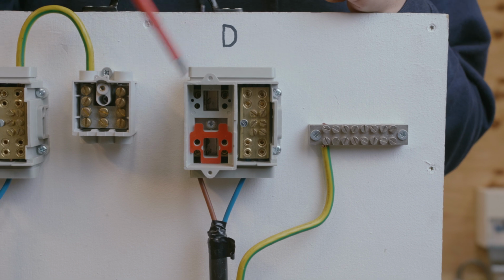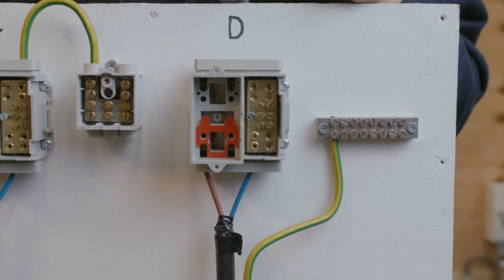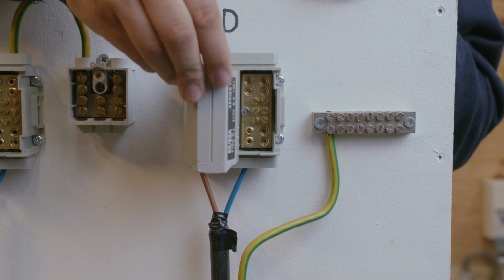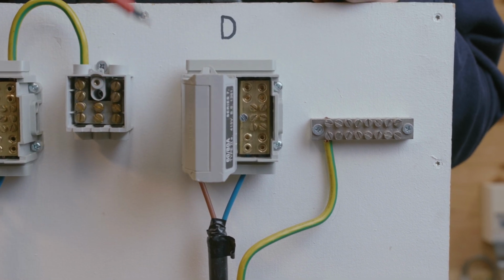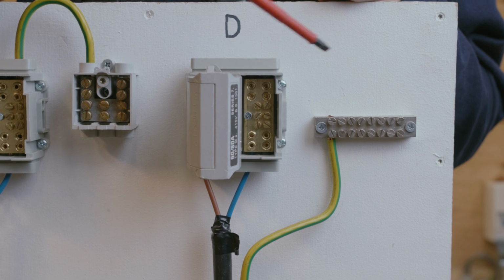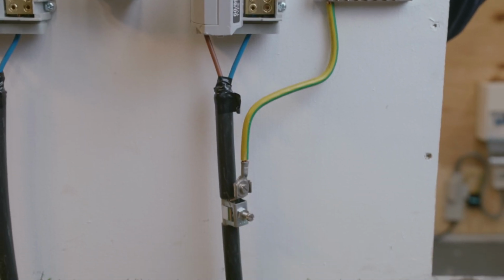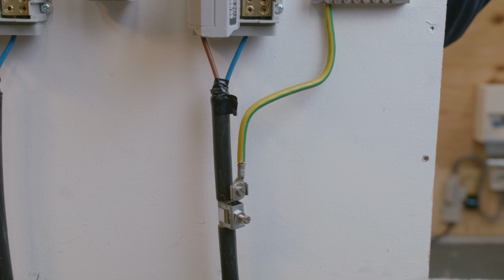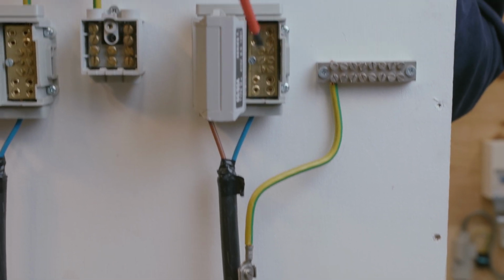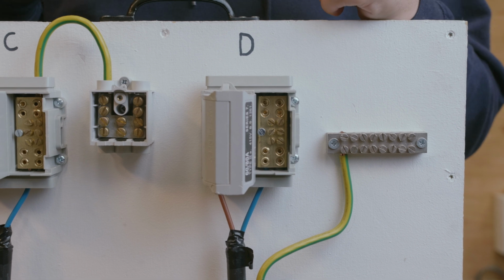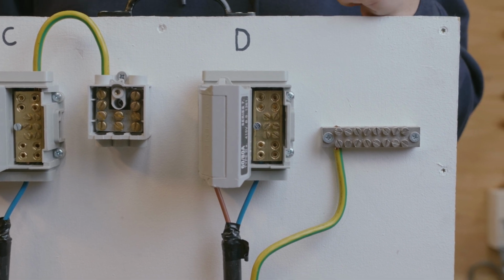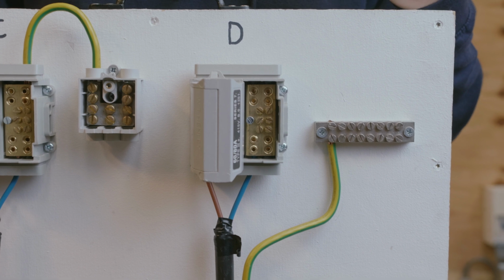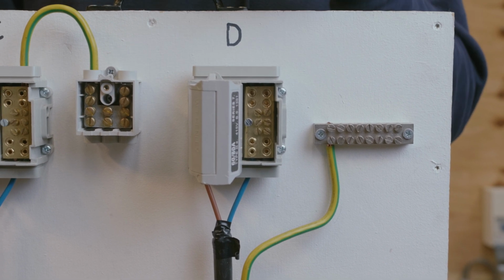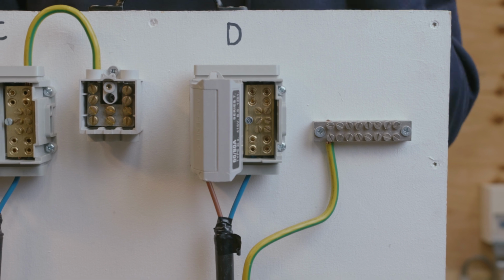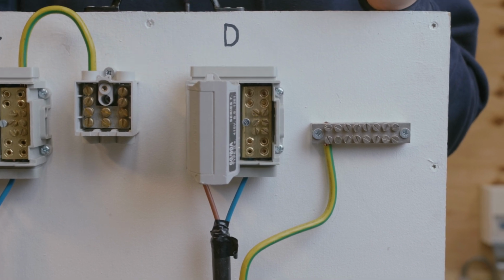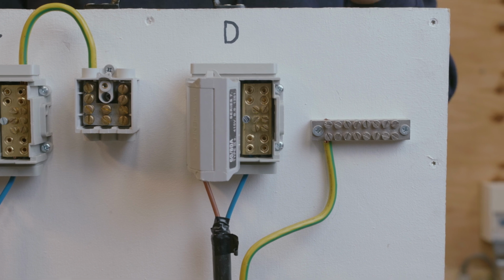Okay, so if you see this earthing arrangement here, and you had your fuse inside and you'd have your cover on as such, then basically how you would identify the earthing arrangement would be the means of this earth attaching to the armourings of the supply cable. Okay, and that would show you that the earth and the neutral are completely separate, as opposed to the one that we looked at previous, which was A, where the only way you could identify that one would be by pulling the main fuse, taking the cover off the cutout, and physically visually seeing the separation within the cutout.